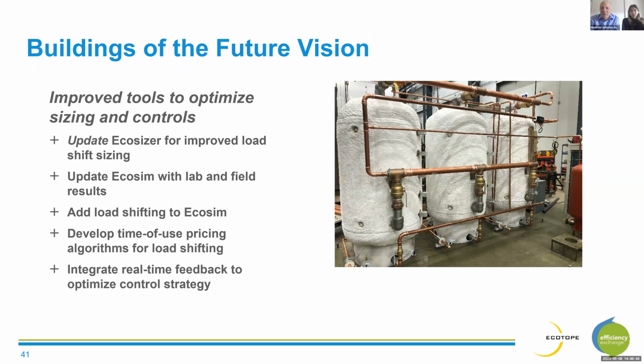And what we see in the future is that, as we get better integration with the utility, knowing that the most likely scenario is that more and more utilities are going to start charging time of use pricing for electricity, electricity in those peak periods will be really expensive, and electricity when there's a surplus of solar will be cheaper. So if we had that time of use pricing picture a day ahead, and we know what the load shape is in the building, we could write an algorithm that could optimize when those load up periods are and when the shed periods are to keep the operation of the equipment as inexpensive as possible for the owner.